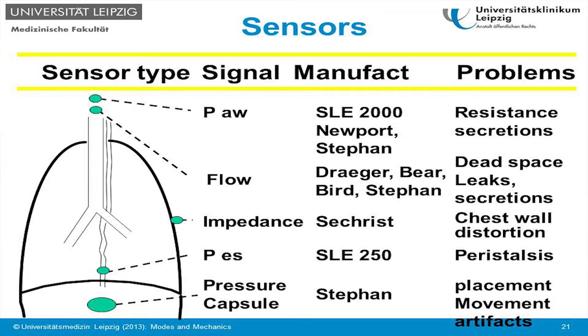So the sensor types: there are airway pressure measurement, flow measurement at the beginning of the airway. The impedance will be measuring the electrical resistance across the chest. Esophageal sensors are prone to artifacts by peristalsis, impedance by chest wall distortion. Flow sensors have dead space. They are prone to leaks and not very good at handling leaks, and also affected by secretions.